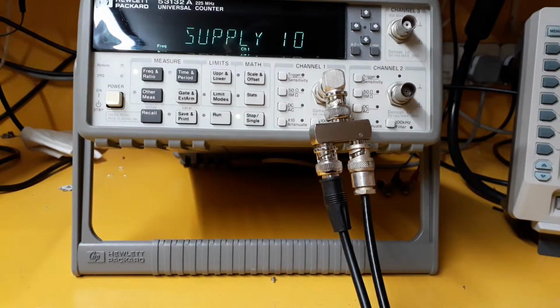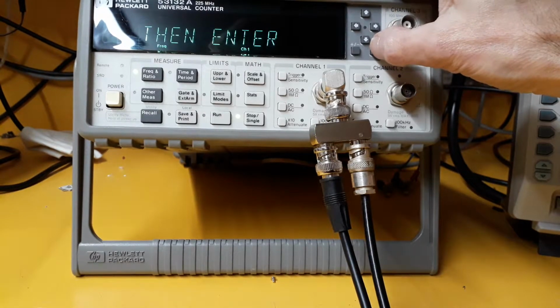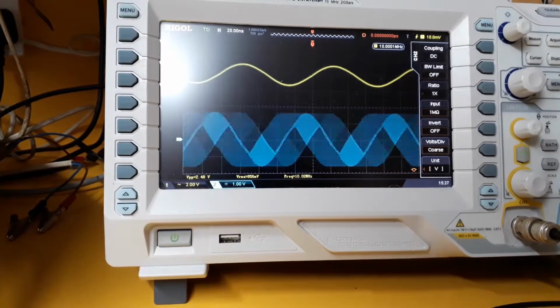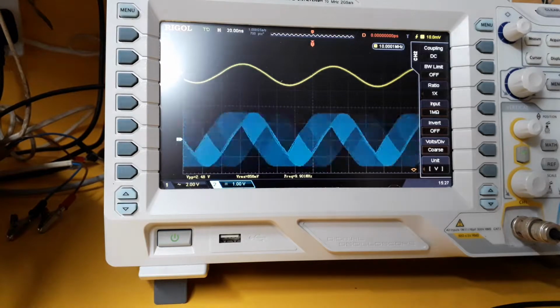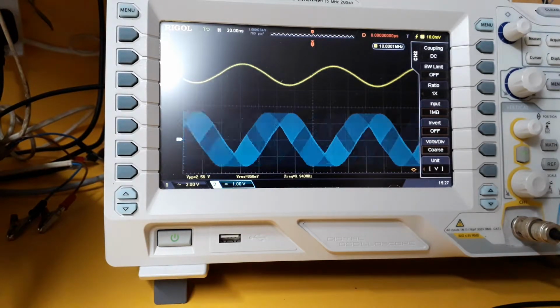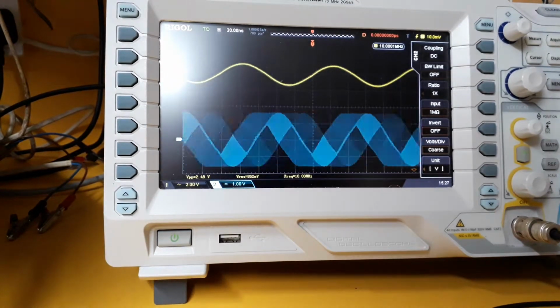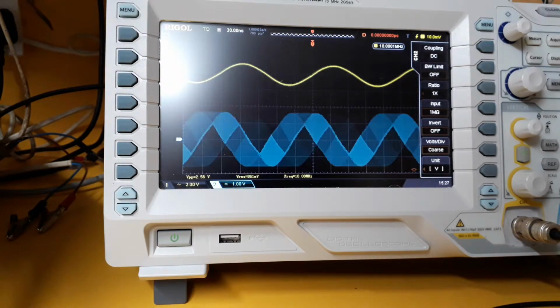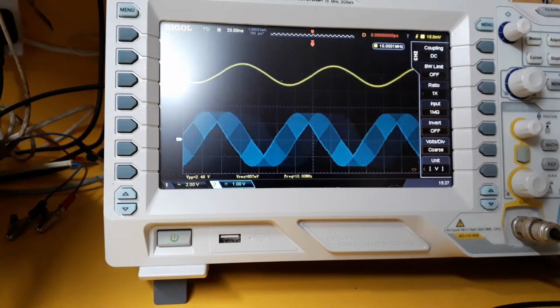Right, it says supply 10 megahertz, which is what I more or less expected it to say. And press enter. So I'll go ahead and do that. Now it's calibrating. Let's go back to the scope quickly. And you can see it's trying to tune the oven. And it can take a while to do this, I believe.